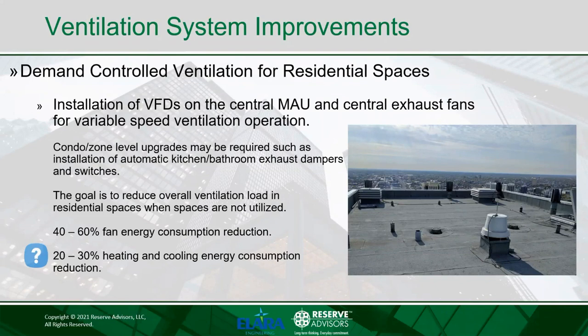For instance, when most bathrooms and kitchens are not utilized at 3 a.m. in a building, the central exhaust fan serving these spaces can slow down and save energy, and that is a significant amount of energy. Please note these projects may require some condo zone level upgrades. These are typically minor upgrades, such as installation of automatic control dampers or switches in the kitchens and bathrooms. And with demand control ventilation in the residential portion of the building, we typically see 40 to 60% fan energy consumption and 20 to 30% heating and cooling energy consumption reduction.